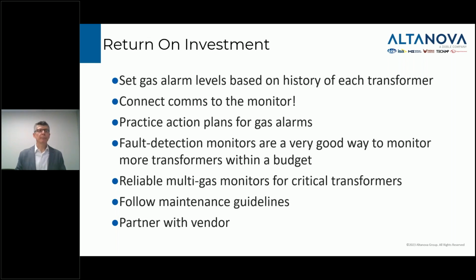Some of these I've mentioned already. If we think about factors important to ensure a good return on investment, the first is to set alarm levels based on the history of each individual transformer. If you're not sure what that means, or want guidance on how to do that, we're happy to help - we have a recommended process for doing that. It's really a low-cost way to ensure you're getting the maximum value out of your DGA monitors.